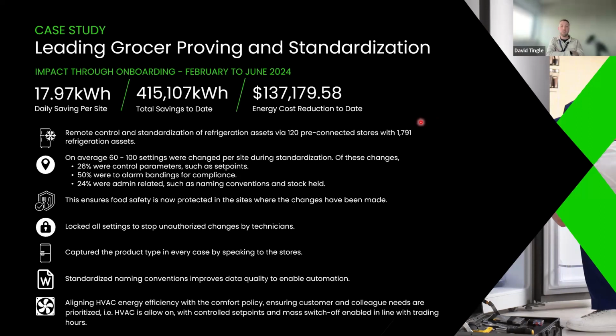It was about standardization, getting connected to all the refrigeration, standardizing all the specs and set points back to spec, making sure settings weren't being changed to get around issues, and managing that end to end. From that process, we saw quite a large energy saving across around 120 sites, just by bringing everything back to spec. That saving was achieved before even trying further optimization. There was also an HVAC element with this customer, so we brought HVAC into the scenario to make sure the two weren't fighting and were working together instead.